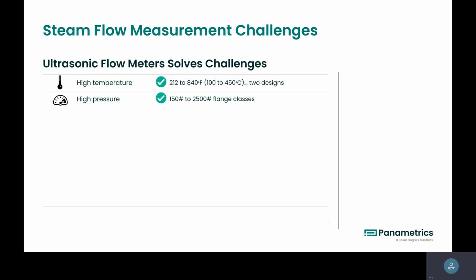And we'll talk about the two ways we do it, but we do have the ability to handle that high pressure overall. And you'll see one of the examples where we actually isolate the transducer from that high pressure. So there's really no safety issues you have to worry about with maintenance of the transducer. Low pressure. With our systems, we can again measure 5-pound steam because we have very little maintenance, very little restriction in the pipe. So it's really just the piping itself. Again, in most situations, we actually don't insert the transducers into the line. So it's really just that piping that's causing any type of pressure drop.